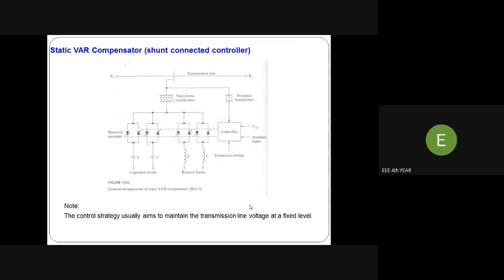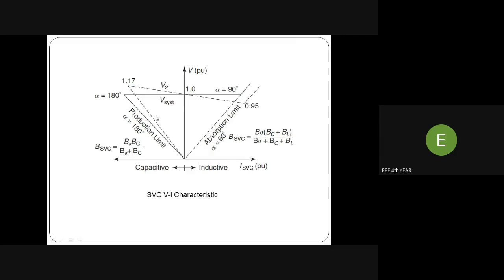So this is the SVC VI characteristics. The left side portion is the capacitive reactive power production limit. The right side of the diagram is the absorption limit of inductive reactive power from alpha 90 degree to 180 degree. Here the firing angle alpha is varied from 90 degree to 180 degree for the anti-parallel thyristor valve. This is the absorption limit, and in the other direction it is the production limit. So always the voltage is kept constant. The only variable parameter is the current, either ISVC inductive or capacitive current.